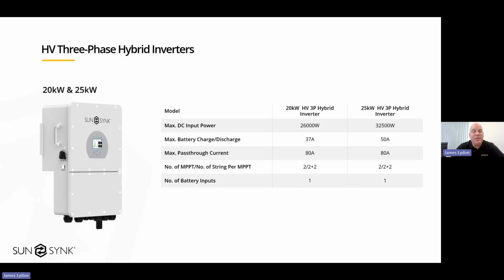Okay, our high voltage hybrid inverters. These are obviously 3-phase, and these will only work with our high voltage batteries. Starting off the range, we do a 20 kilowatt and a 25 kilowatt. You can see the max DC input power there: 26 kilowatt on the 20 kilowatt and 32.5 on the 25. Each has 2 MPPTs with 2 strings into each, and each has 1 battery input.